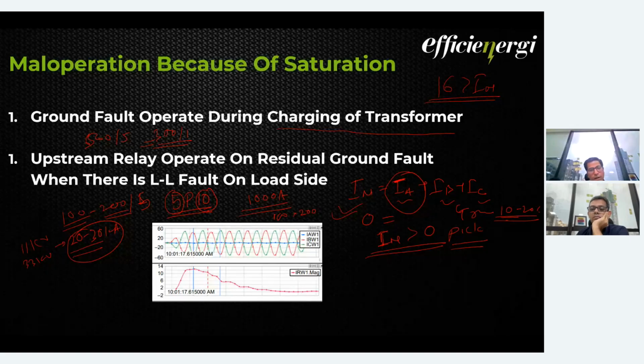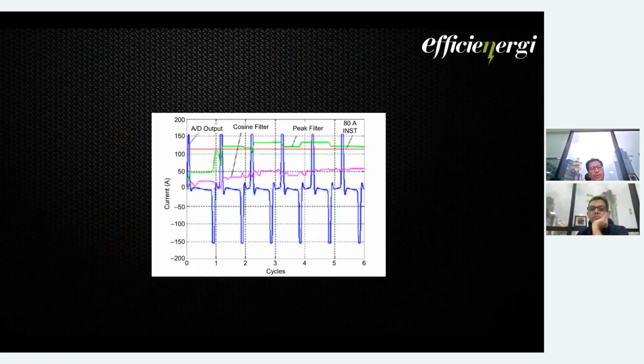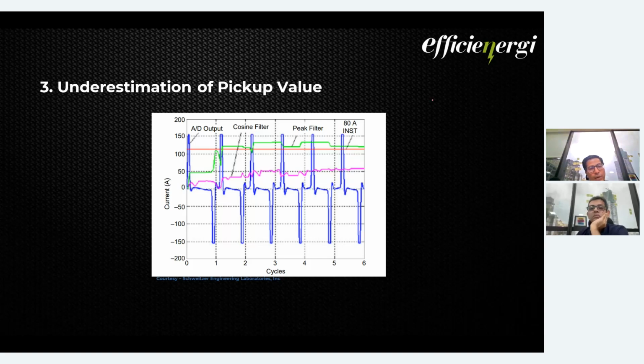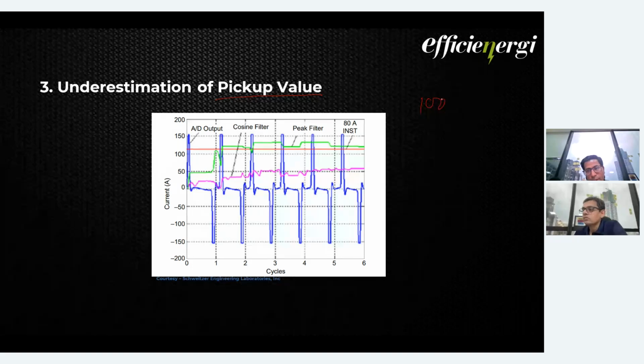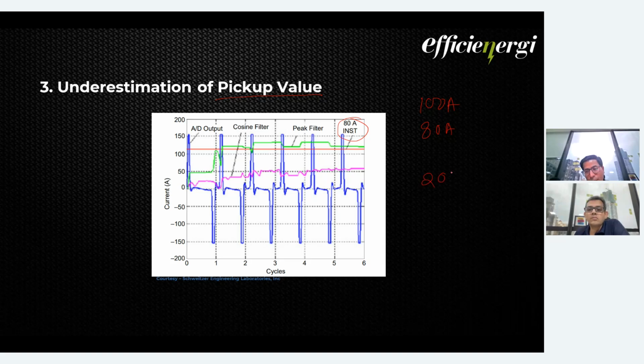Okay, the third point is underestimation of the pickup value. So if you see the same case where you have a 100 ampere CT and you are setting it at 80 ampere. Here is the case. Here 80 ampere is set. Okay, and the fault is actually 20 kilo ampere. So it's a heavy fault, and so this CT will not handle this much fault.